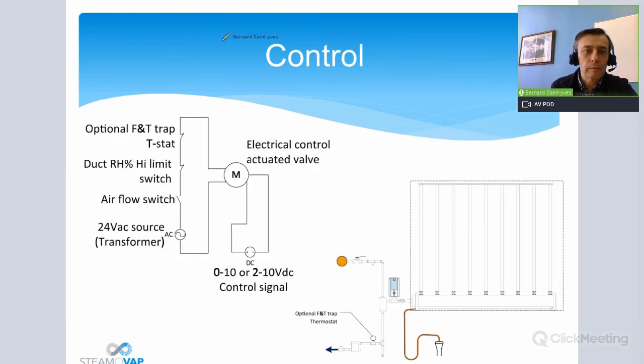So the control, usually it's very simple. I always say simple, but you have to know it to find it simple. So basically, you always have an airflow switch, a duct high limit, and a relative humidity switch, or humidistat, to protect your system against any over humidification.